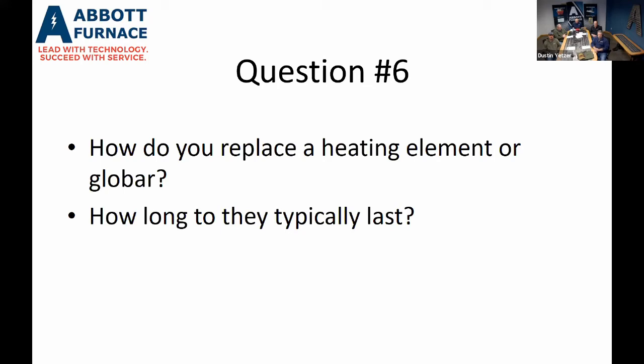So when you replace heating elements in a preheat, you can do one at a time. If you have one bad heating element, you can replace that heating element if it broke, or the support tube broke and it cracked your heating element, and you don't have power going through it. You can replace the one without any degradation to anything else in that zone.